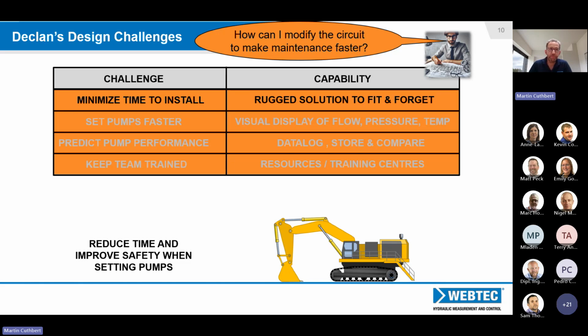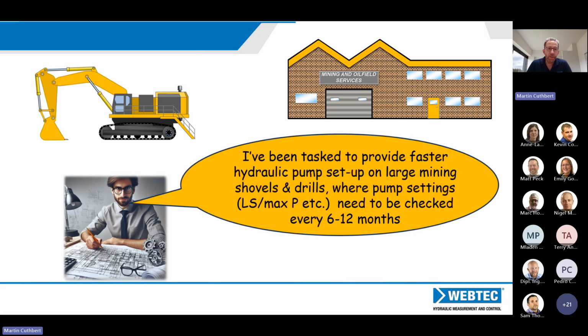And why is that important? Well, here Declan's talked about it. He said, I'm tasked to provide faster hydraulic pump setup on large mining shovels and drills, where the pump settings on a load sensing pump, maximum flows and pressures, need to be checked every 6 to 12 months.